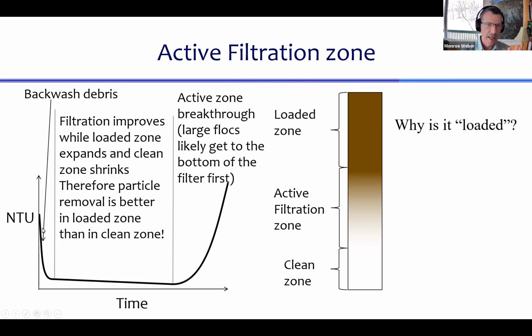There's this initial period when performance is bad. It's a combination of backwash debris that was left from the previous time the filter was cleaned that might be coming out initially. And there's something about the filter loading that makes performance better than if it were just clean sand. It's something about the particles coming into the filter that actually improves the subsequent performance of that filter.